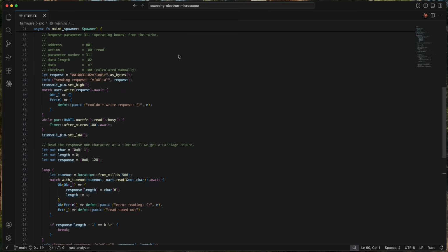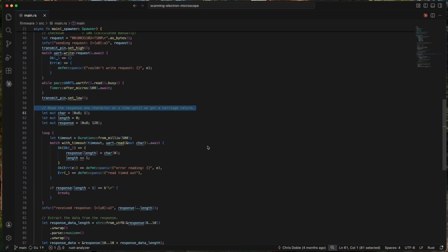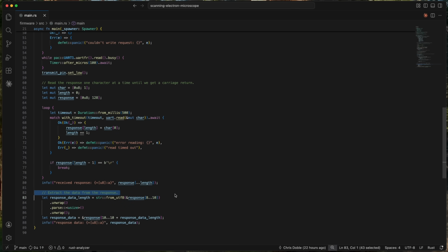We need to craft a message in the format we discussed earlier. The turbo's address is 001, we're reading a parameter, the parameter number is 311, the message data is an equals sign followed by a question mark to indicate we're asking for the parameter's value, and I've calculated the checksum manually. So we send that message, read the response, and extract the response data, which should be the total number of hours the turbo has run.